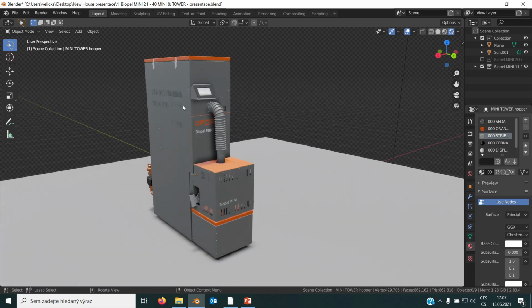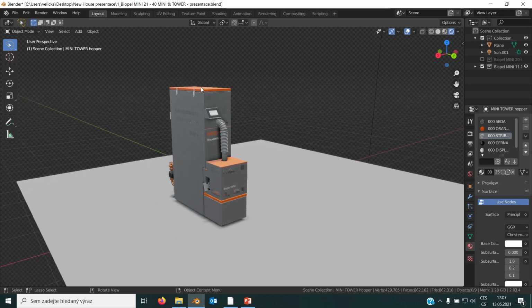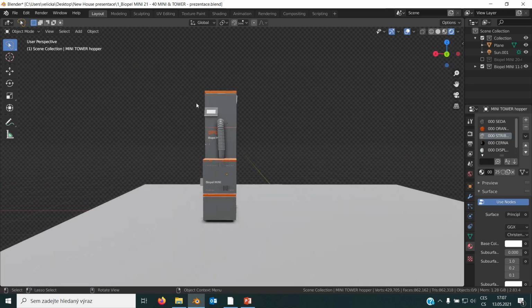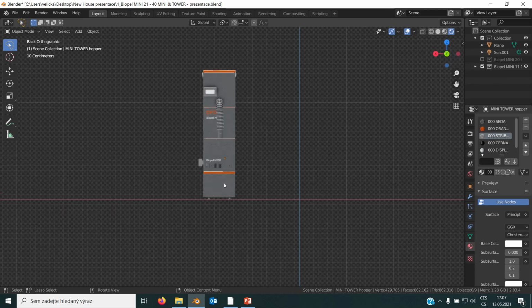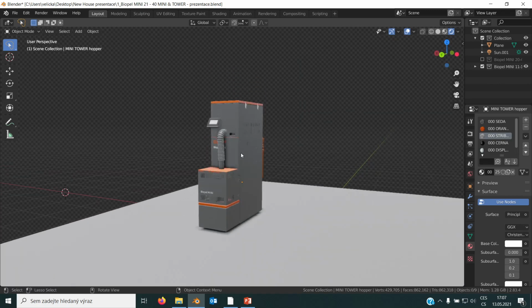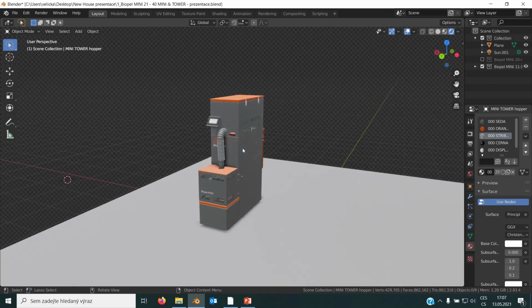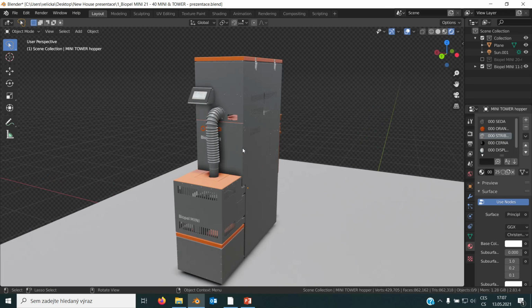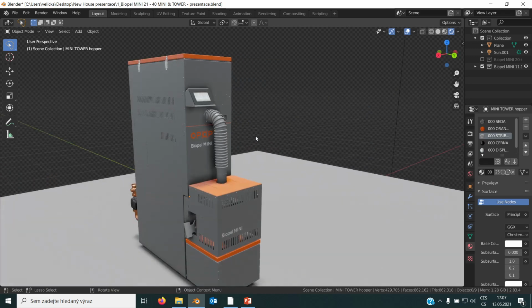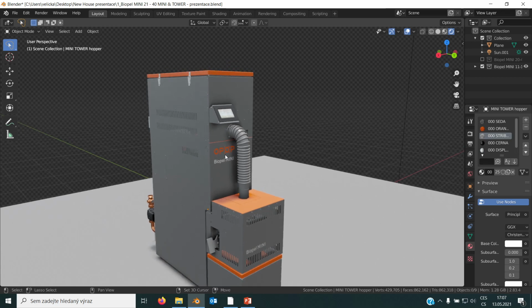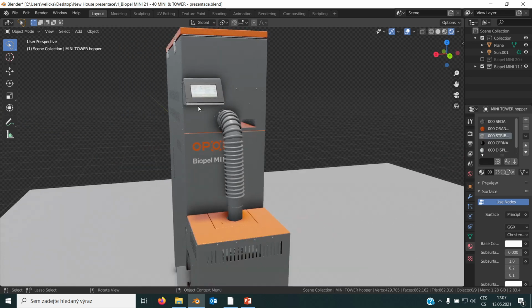So if the power is judged properly, then I think the pellet hopper will last for 1 day with no problem. Of course, you have a small boiler, 36 centimeters wide. This is an advantage. The disadvantage is that you have to fill the pellet hopper once a day to make it work properly. Okay, but otherwise it is really again the same type of operation with the same control unit installed on the left or right side.